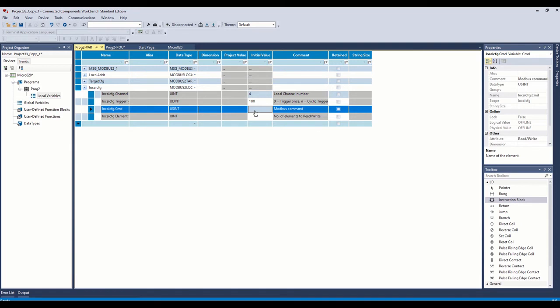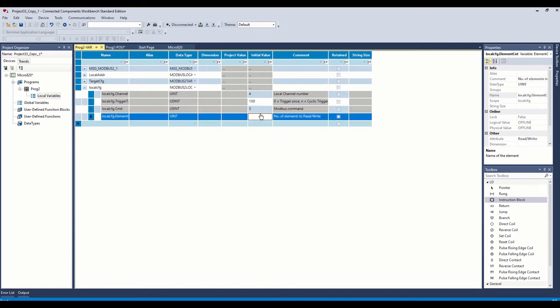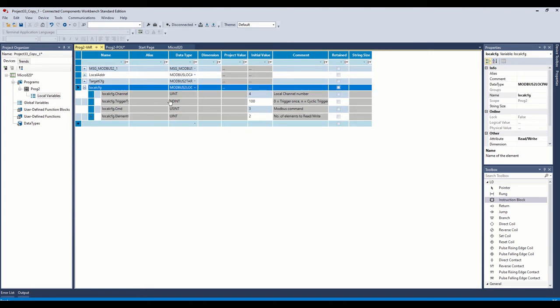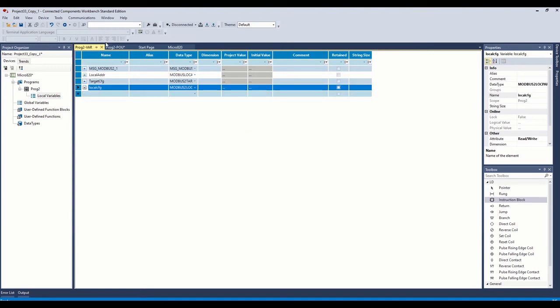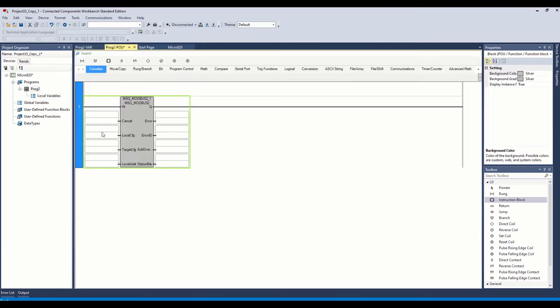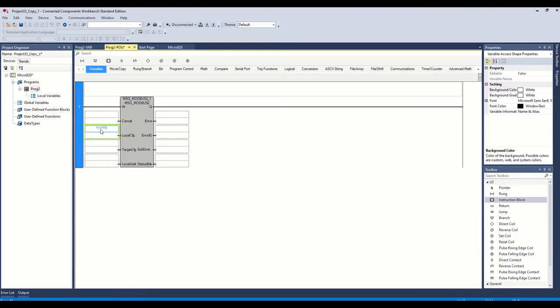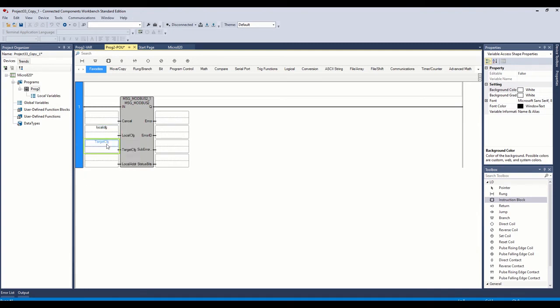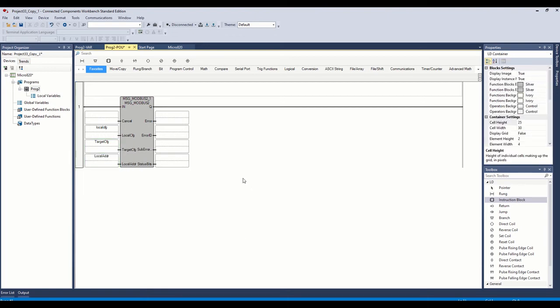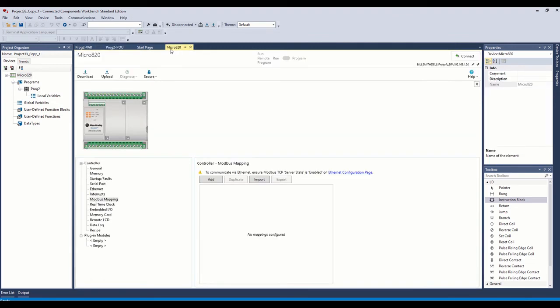The Modbus command three is what we're going to put in cause that's our read multiple holding registers. And we're going to go ahead and read two of them just for this example. So we're going to read two holding registers and the information will get put into this local address. So our next step is to come back over to our program and type those tags into these fields. And we'll save.